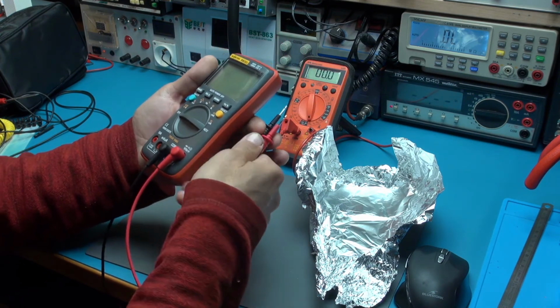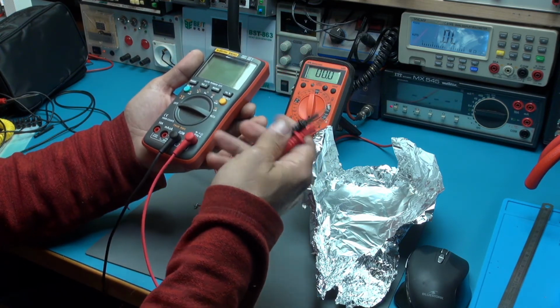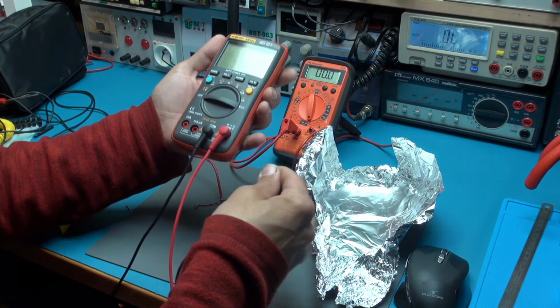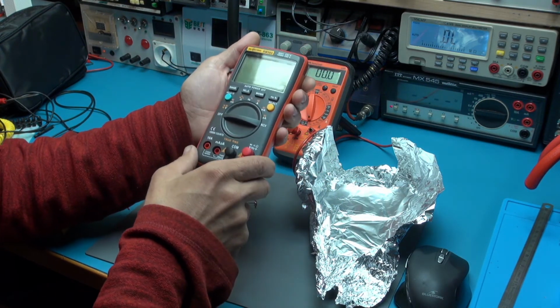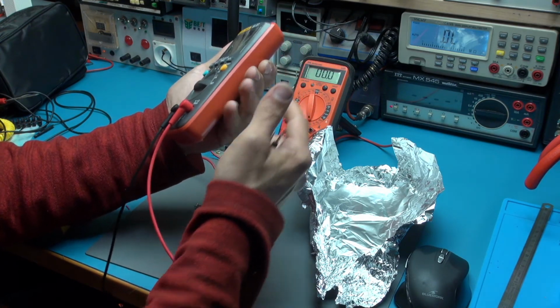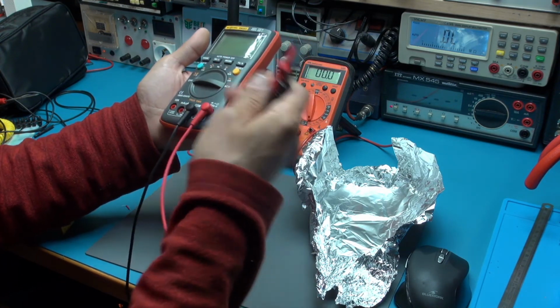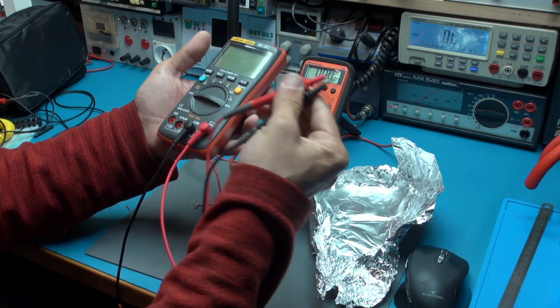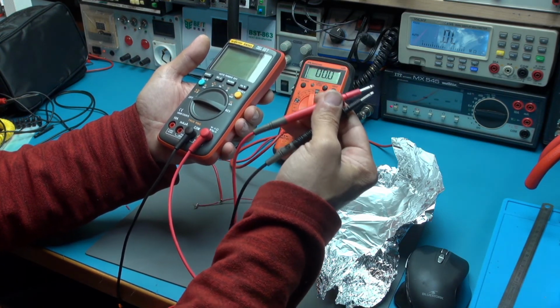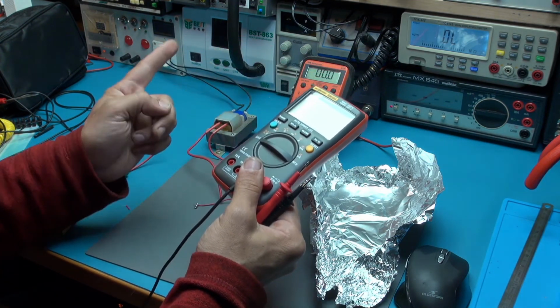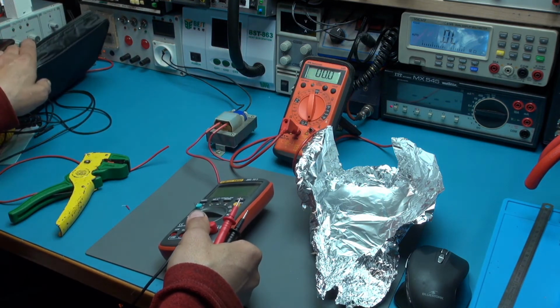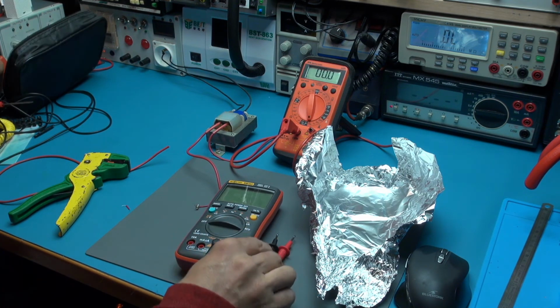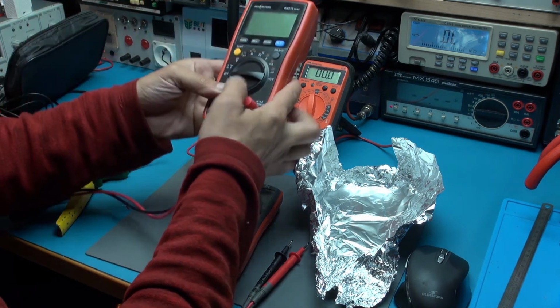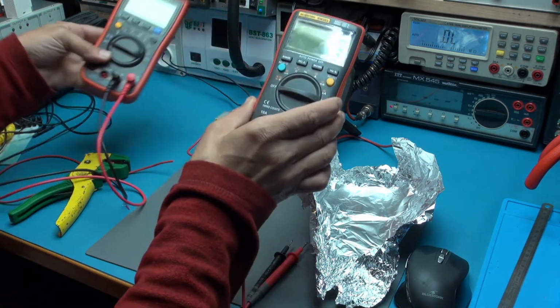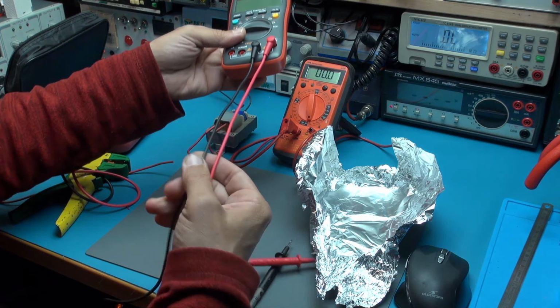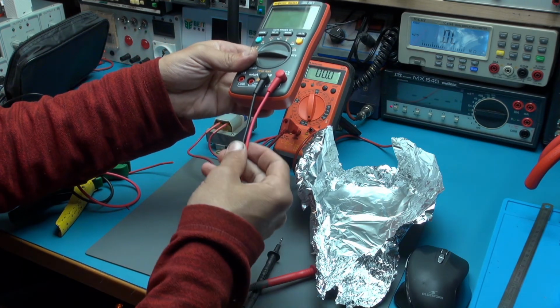If you have 4,000 volts on the leads, you can have 70 microamps through your hands, if you are at 4,000 alternating voltage. Let's do the same test with this one. Of course, each device is tested with its own proper cords.